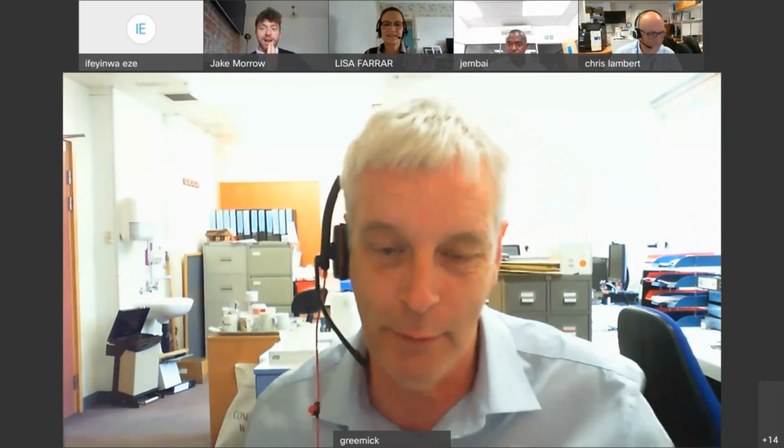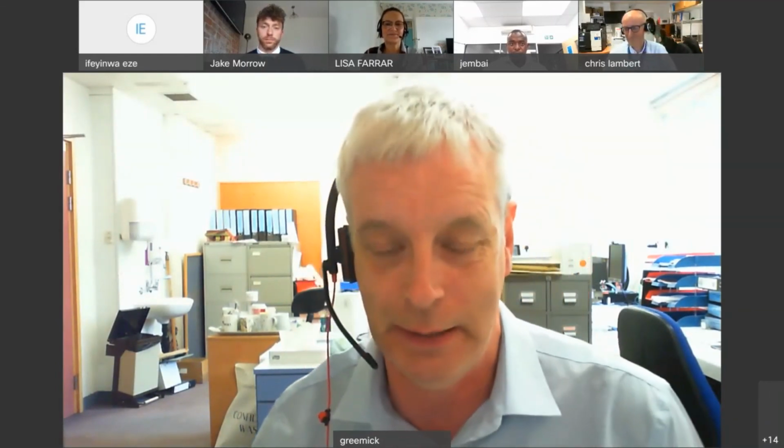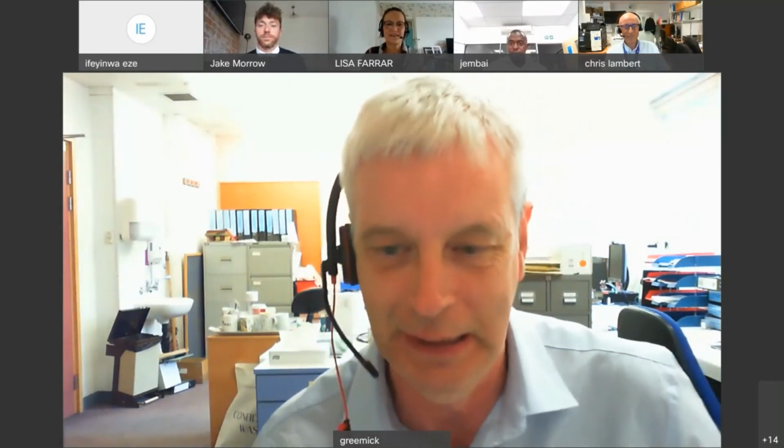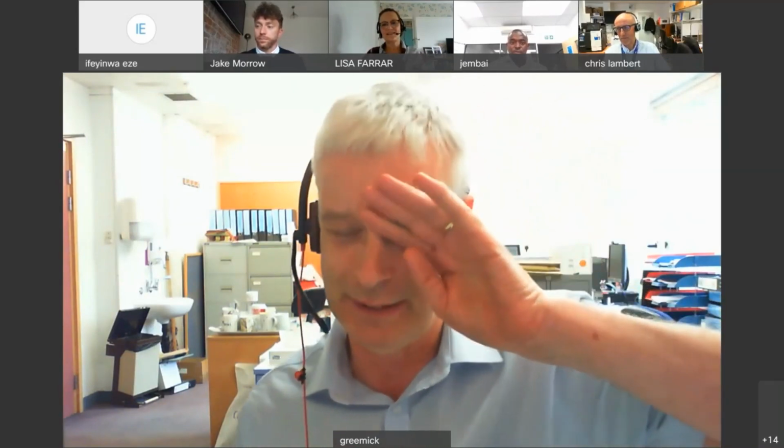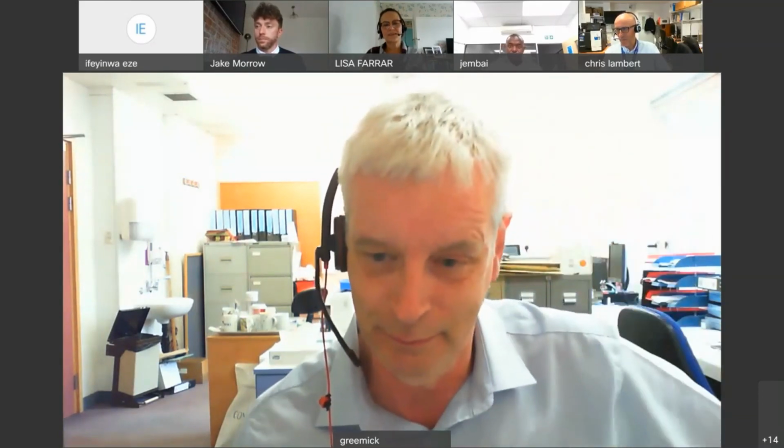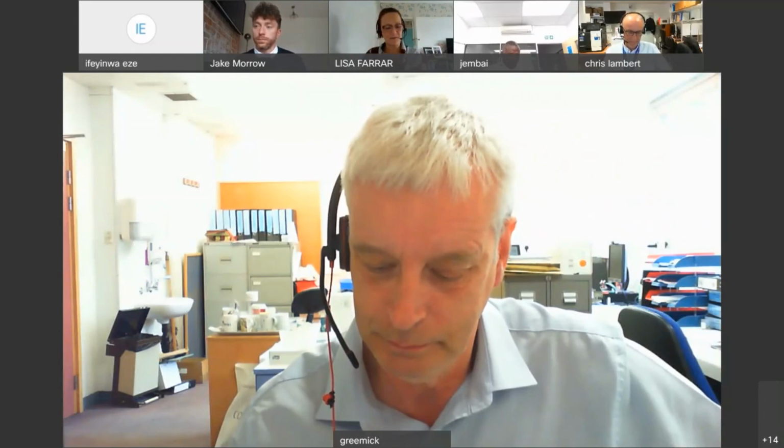Because it seems to bias it against the bigger users, and obviously we're in the group here. We've had a similar problem to you, Lisa, that we're a Tosoh user, and we seem to have a negative bias on A2 compared to, like, Bio-Rad, so to speak. But obviously within the group, everybody's an overall mean. From UKAS's perspective, you have to do a non-conformance because your DI goes above 2, but within the group you're not.